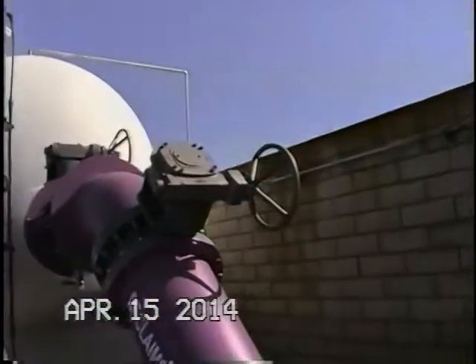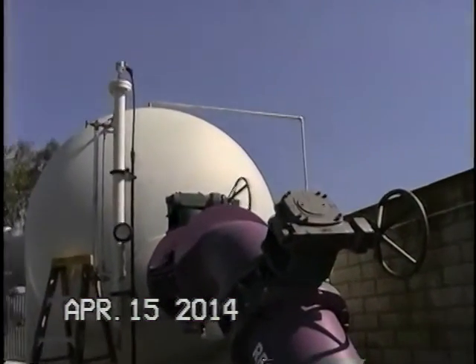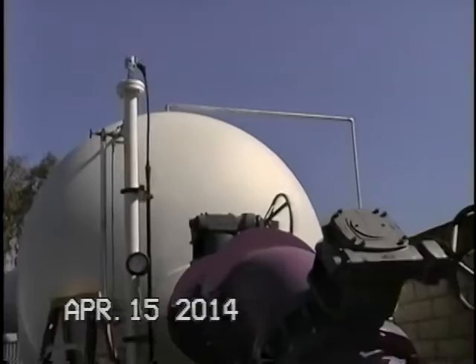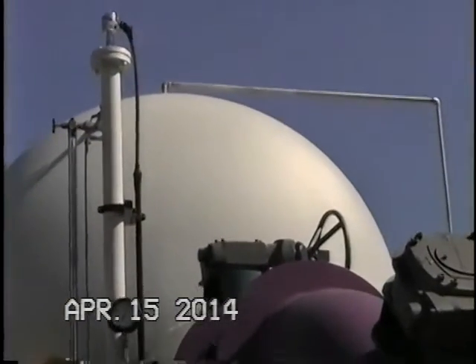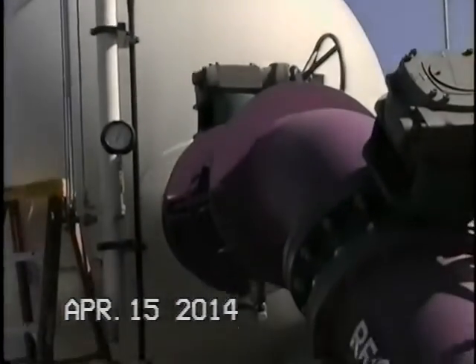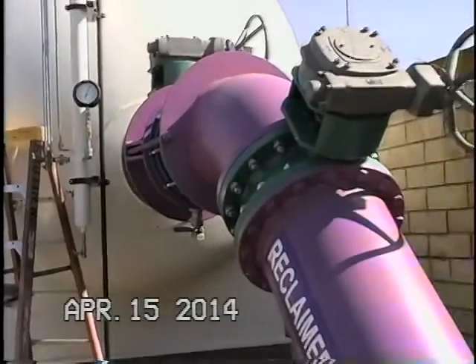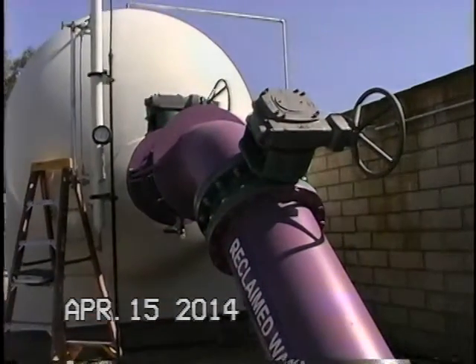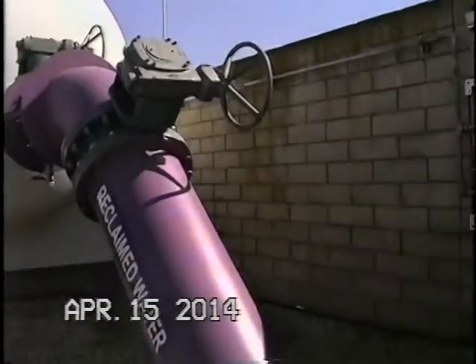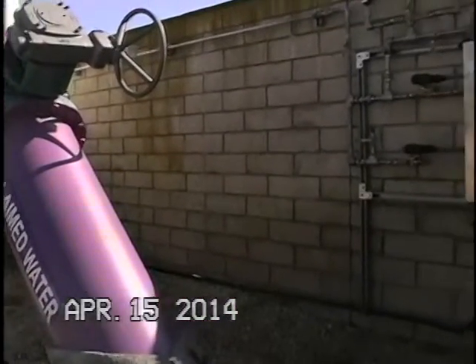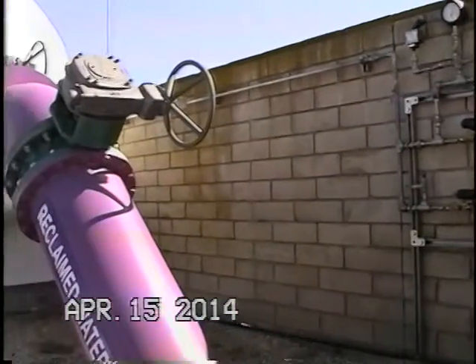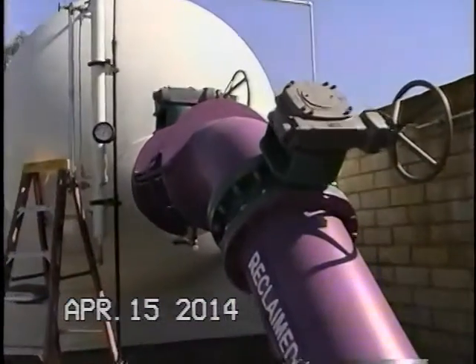We prevent that with our liquid level controls. We have a probe well, which in this case has a single probe, and we'll get to that in a little bit. We'll go over what we have. We have a sight glass, so we have visual indication of what's going on inside the surge tank.